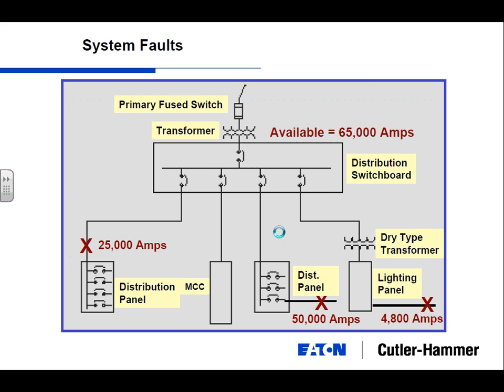Here's another one. This one dropped noticeably down to 4,800 amps. What's different about this lighting panel? Well, this is 480/277. It's a dry type transformer that's stepping it down to 120/208 for your lighting panel. And this could be the exact same distance as this one from the switchboard. So what's different? What's the key? Why did the fault current all of a sudden drop?